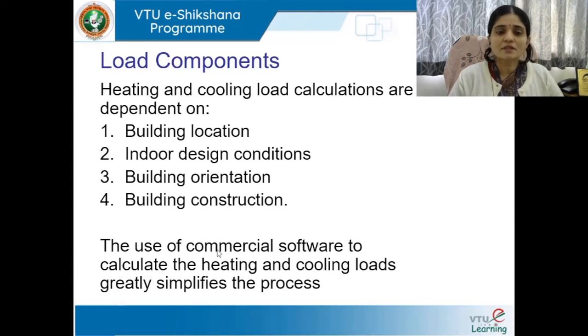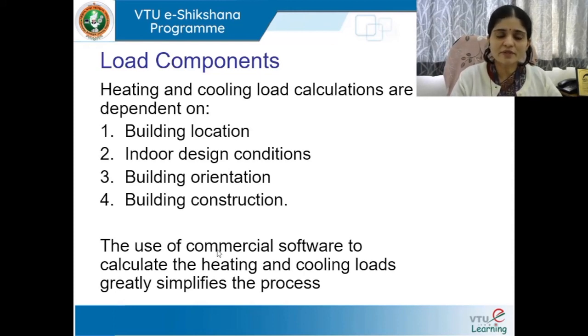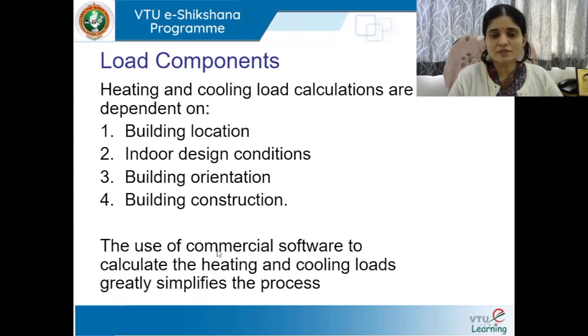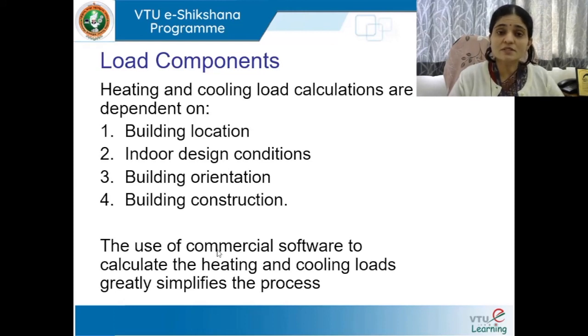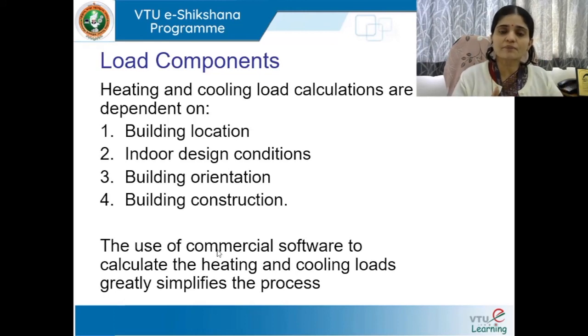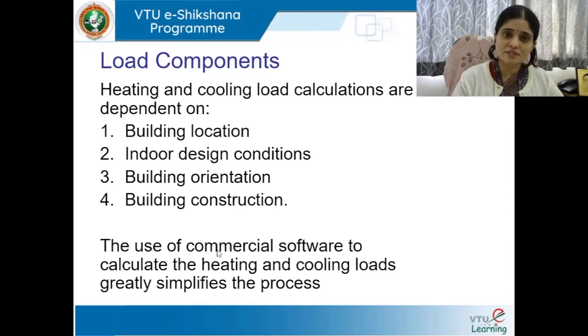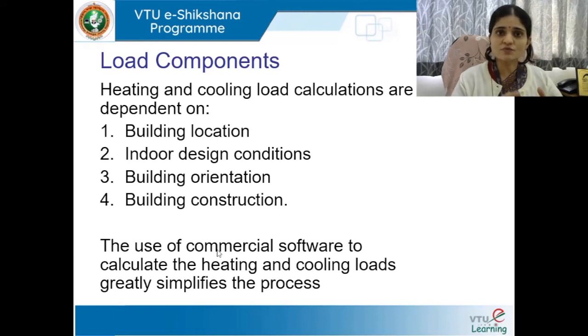To begin with understanding heat load components: heating and cooling load calculations are primarily dependent on four aspects — the building location, indoor design conditions, building orientation, and building construction. Why are we wanting to understand heat load components and calculations? When we are designing a building space for air conditioning or mechanical ventilation, we need to know the total heat gained by the building. Only then can we calculate the capacity or cooling load of our air conditioning system.